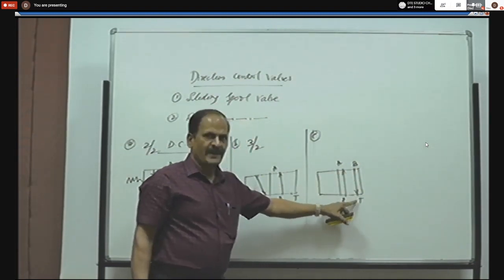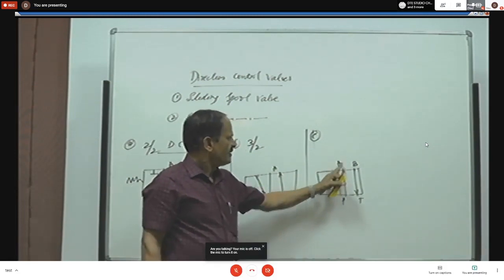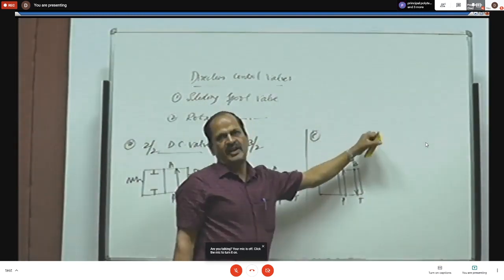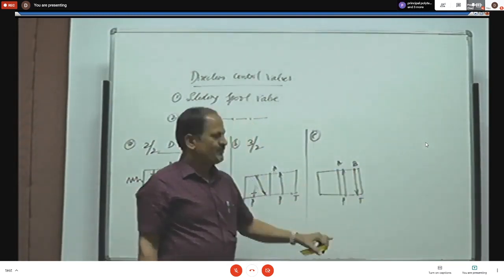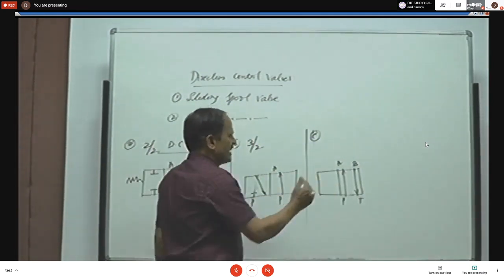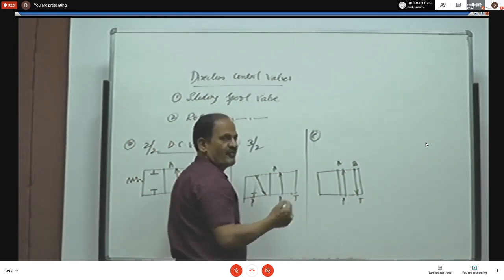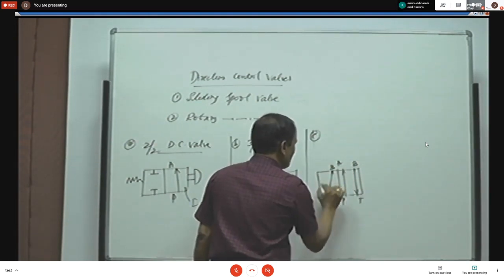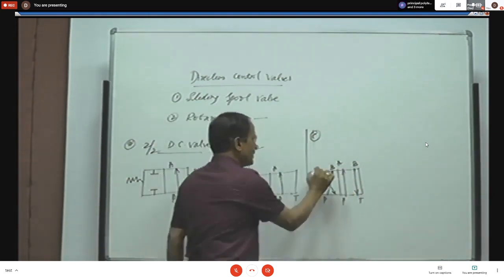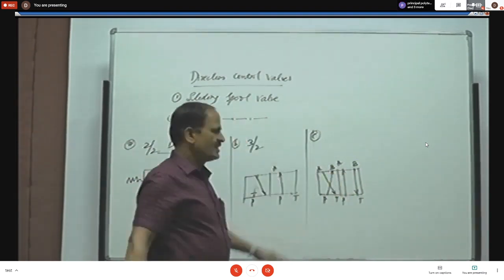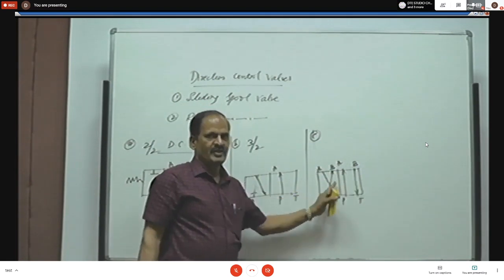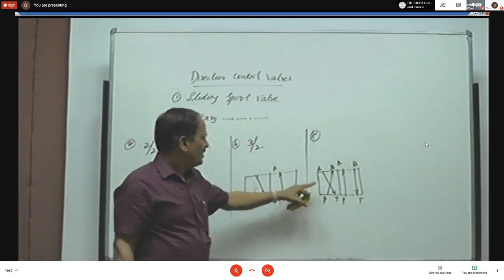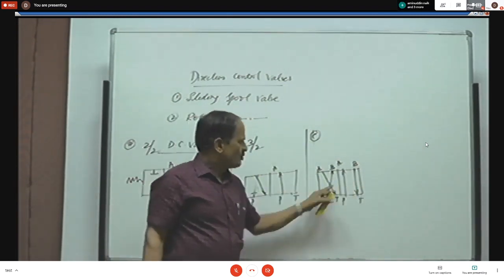In the case of 4x2, there are two positions. In the first position, fluid flows from P to A — fluid enters one end of the cylinder and some work is done. The fluid present at the other end of piston is returned back to the reservoir from B to T. In the second position the direction of flow is reversed: fluid flows from P to B and returns from A to T. So in both directions the piston can be reciprocated. This is the symbolic representation of a 4x2 DC valve.